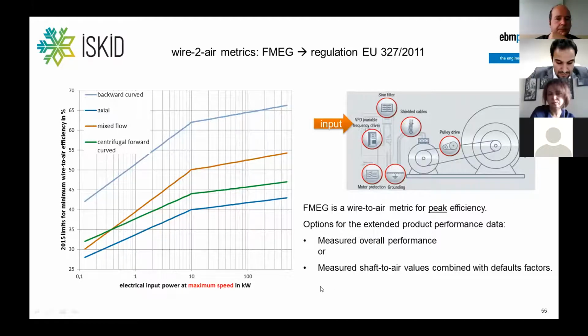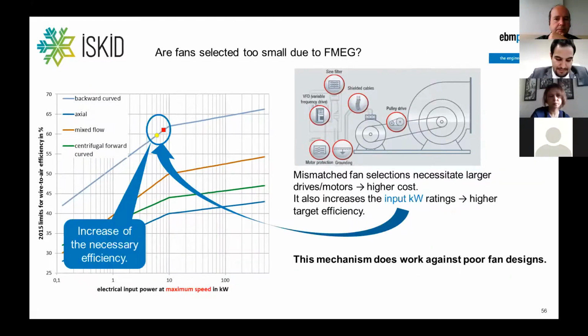So this is closer to reality compared to FEG, because as you see here, the input power is tested versus the output of airflow and pressure. And this mechanism does work against poor fan design. So it has nothing to do with the installation. It's a pure metric to compare, or to take, for example, inefficient machines out of the market. So that was the overall target of the EU Commission when implementing this measure. And you see with a different input rating, the efficiency requirement is changing.